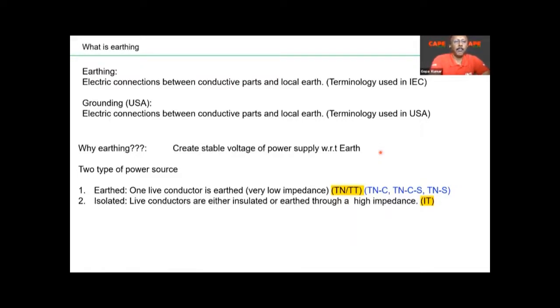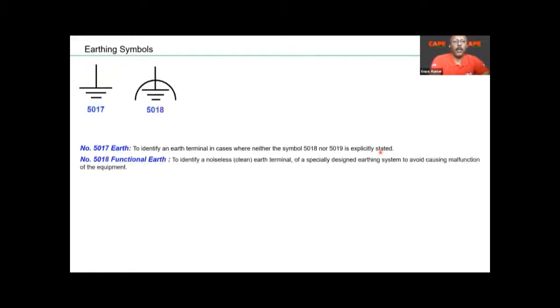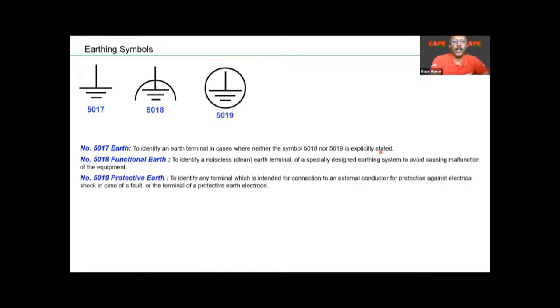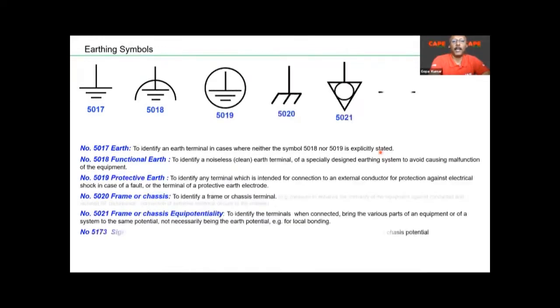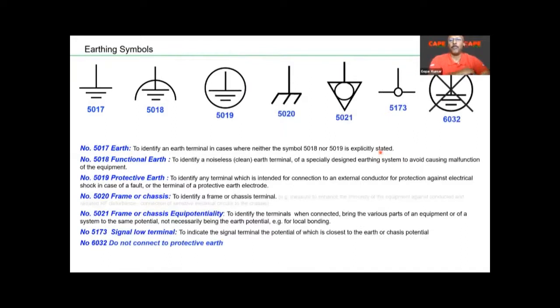Similarly, the second type of power source earthing is isolated earth. Isolated means the current carrying conductors are either completely insulated from the earth or connected through a very high impedance, and basically this is called IT. Now, in order to make earthing, first you should understand what kind of earthings there are and what the purpose of each and every earthing is.